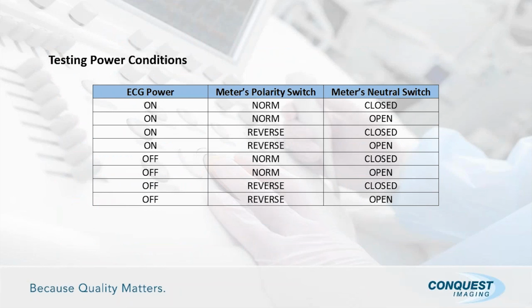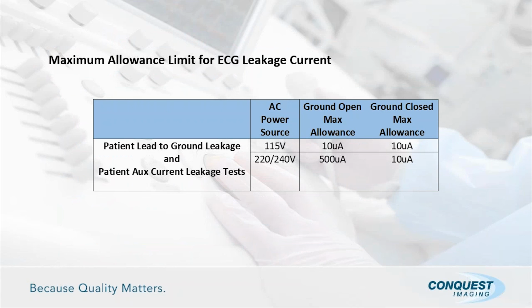And here are the different testing conditions that you have to be in. Again, it's the same as we've seen in the past: on, off, normal, reverse, and open, closed. Record the conditions and report the highest, the most unsafe condition. When you talk about patient lead to ground leakage and patient auxiliary current leakage tests, these are your allowed tolerances: 10 microamps, and at 220/240 it's 500 microamps, or 10 microamps when the ground is closed. So you have your different conditions, and you just need to report and make sure you're inside of the tolerances.